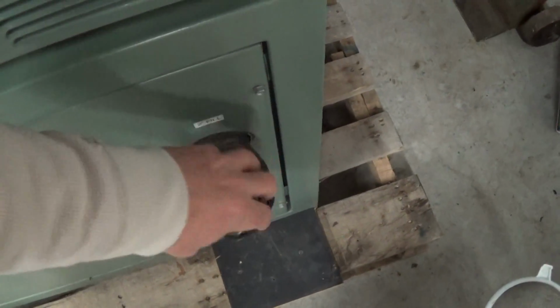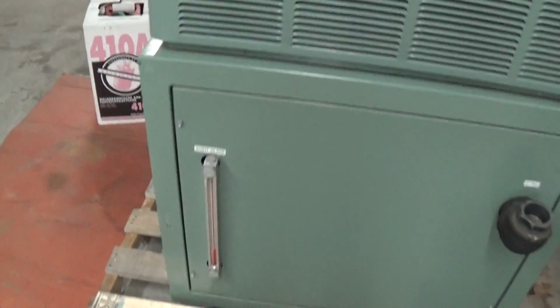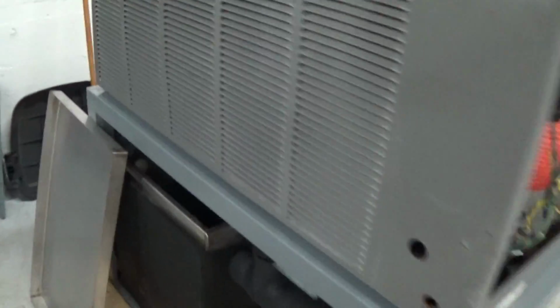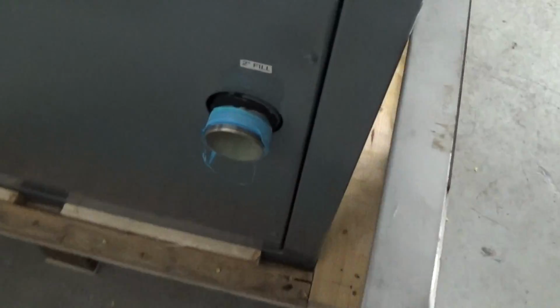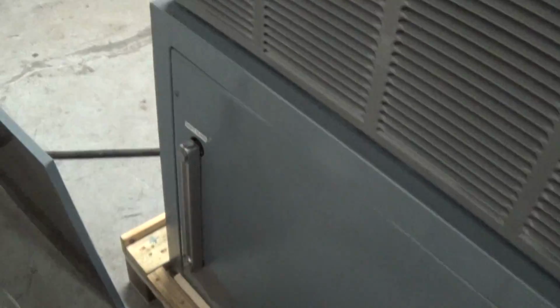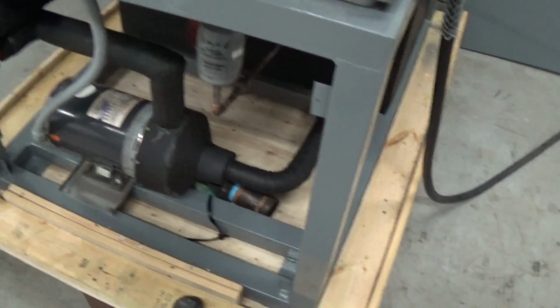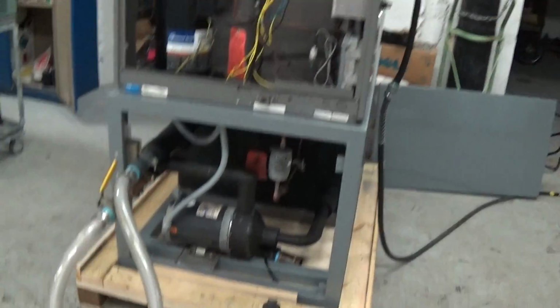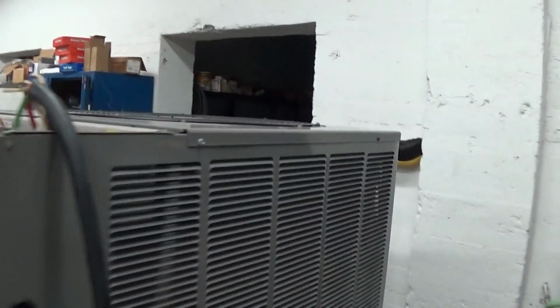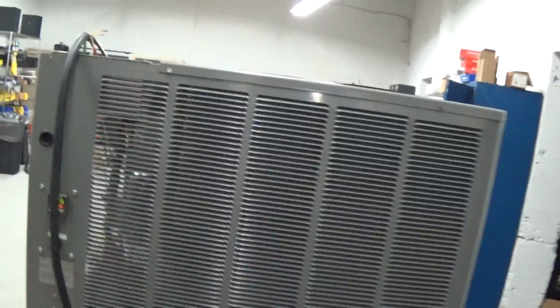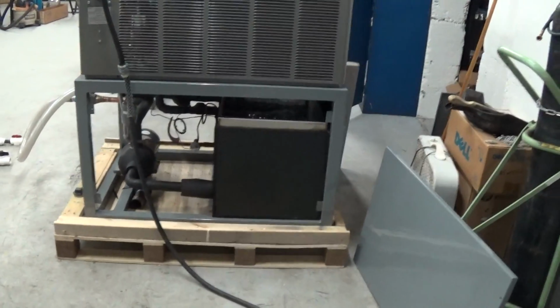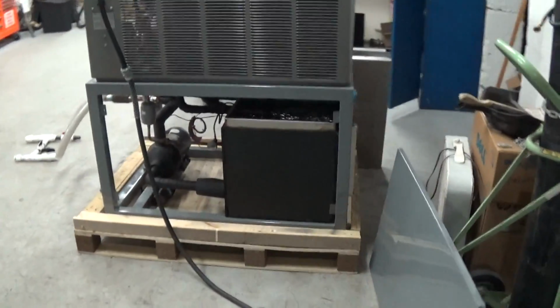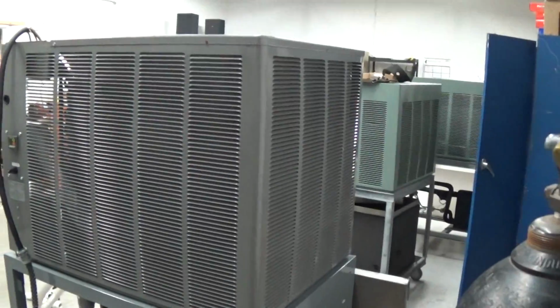It's one of our favorite designs for quick monitoring of glycol level, assuming you don't have a sight glass like that. So in your unit here, it's shipping like that. Again, it'll be inside a crate. You do have the glycol level sight glass. But when you get it, just screw that elbow there onto it. So this unit is solid, well tested, brand new heat exchanger, newly painted on the bottom. It really didn't need it, but our technicians wanted to make it look pretty in addition to making them run perfect, and that's kind of cool.